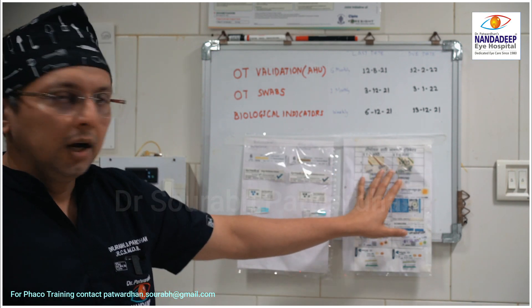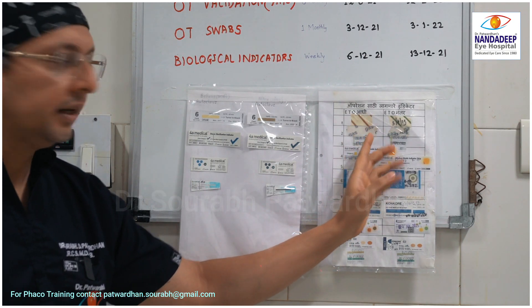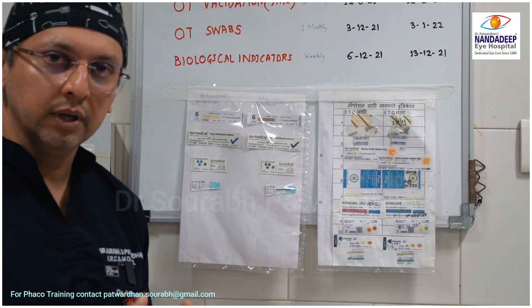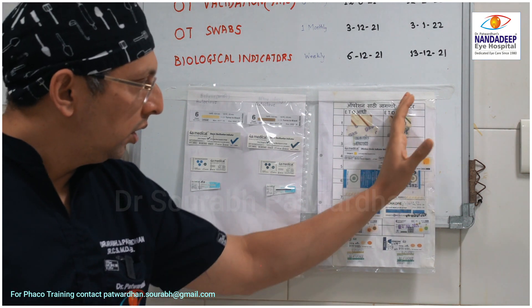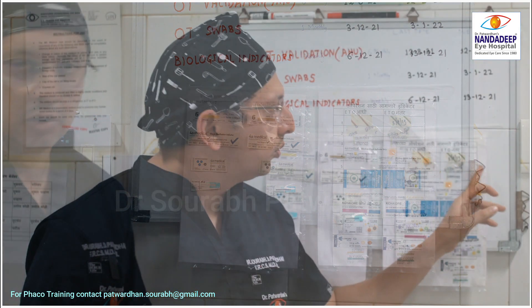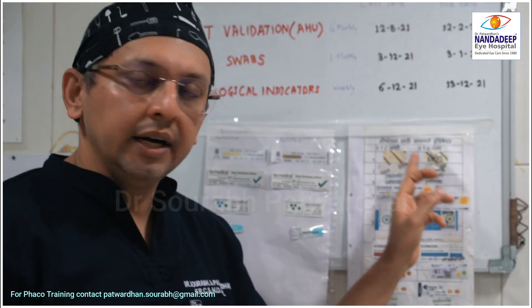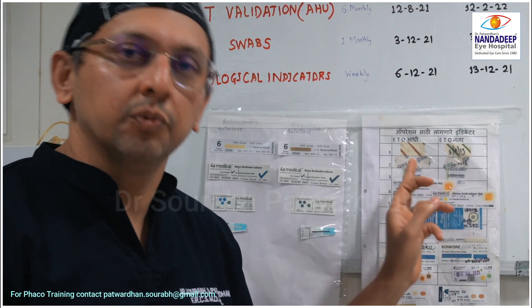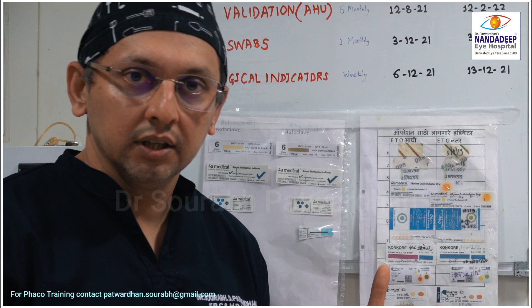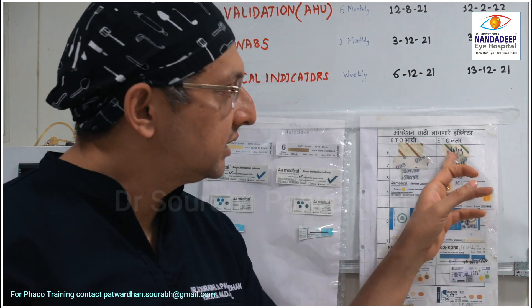This is a chart of indicators showing the color before the procedure and how it looks after the procedure. Because we use different types of indicators and batches may change, every assistant and every surgeon should know whether the ETO indicator or the autoclave indicator has successfully passed the process. You also have to watch for the date or batch number written on these indicators, as the return dates tell you whether it has been used just once or accidentally reused, which could falsely indicate processed surgical material.